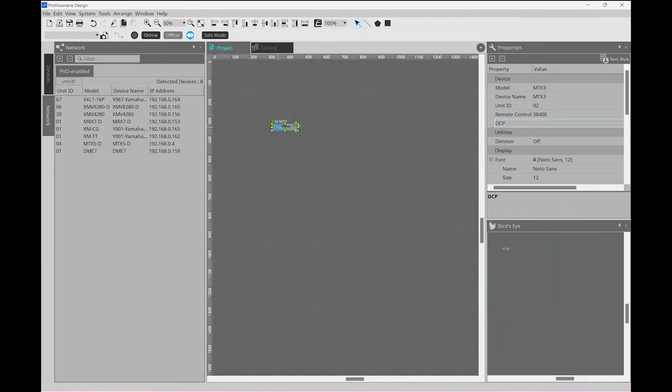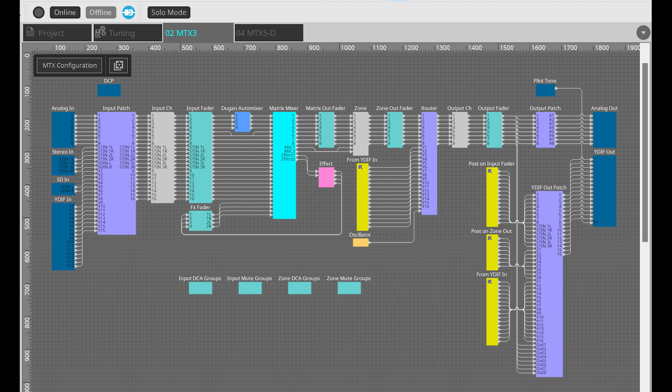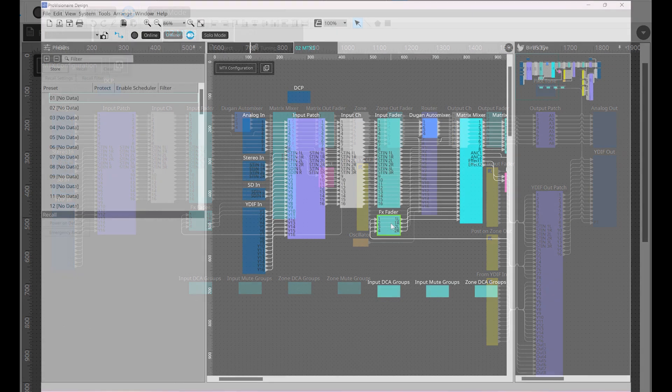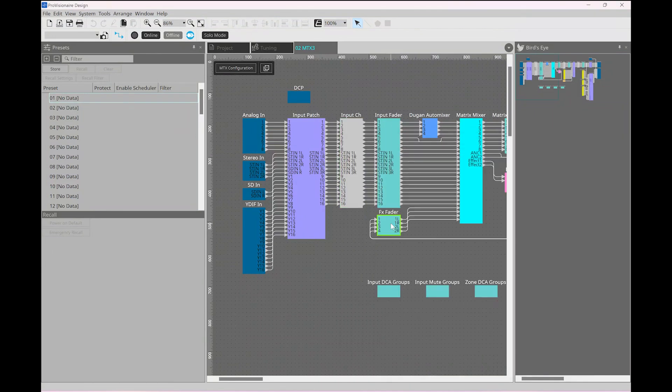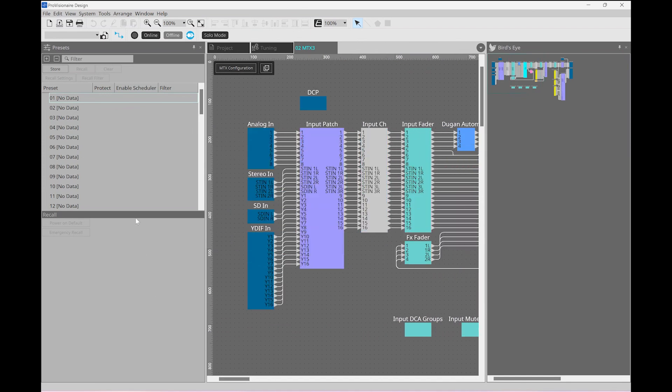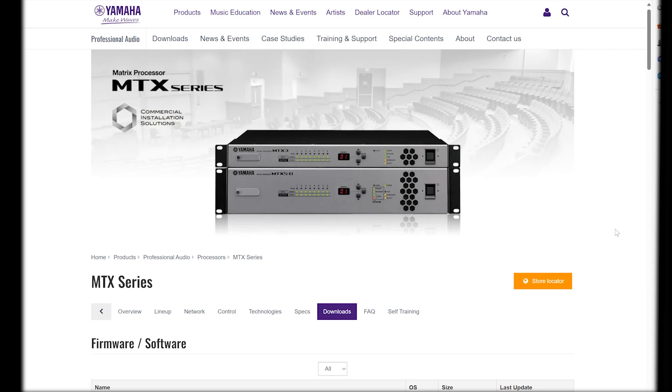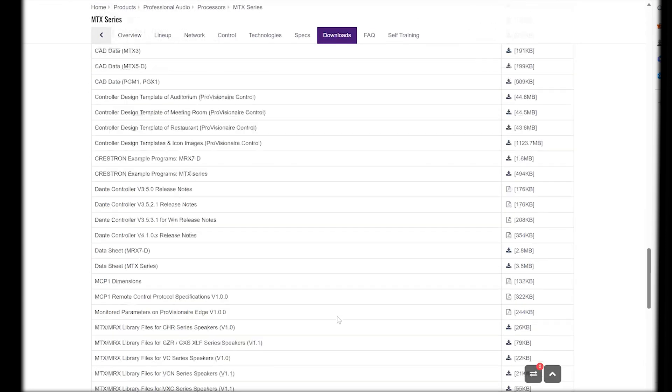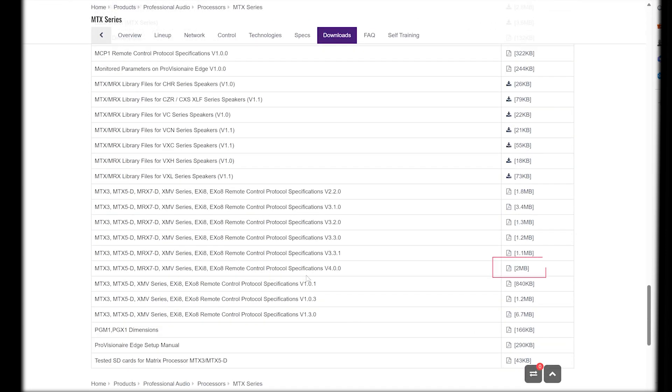Double-clicking on the MTX3 device will open another window where we'll see a schematic showing the layout of this device. This is how the system is configured internally. We can then click on any part of this and edit the parameters within. Every setting can be altered, and as we do this, we can save presets on the left-hand side, which we can then trigger in a number of ways. We could trigger these through our DCP panel, however we could also trigger them through a contact closure or by using a remote control command.